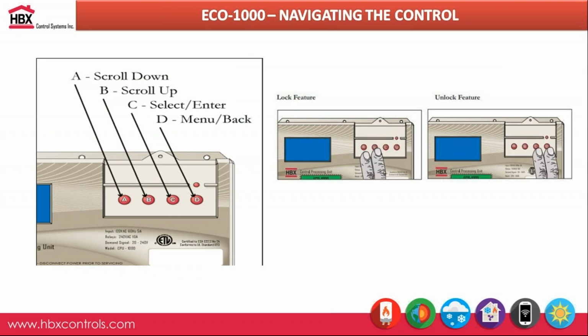So in terms of navigating the controller, it's very easy with the Eco 1000. You have 4 buttons: A, B, C, and D. A and B are to scroll down and scroll up. C is your select, to select that parameter and enter. And D is to get access to your menu or get back to your previous screen, in terms of backing out of the controller.